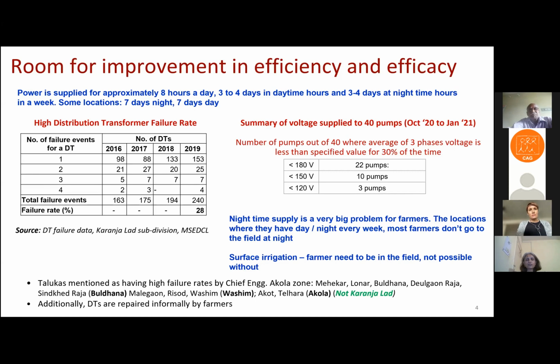A distribution transformer is the last point where the LT network, or 240 volt network, starts, and you might have 25 to 30 farmers connected to one distribution transformer. If a distribution transformer fails, it can take anything from 8 days to 2 months to be repaired. This is especially a problem because distribution transformer failure is very high for agricultural transformers, and the failure rate is very high in the peak season.